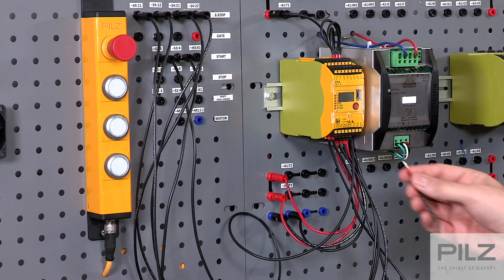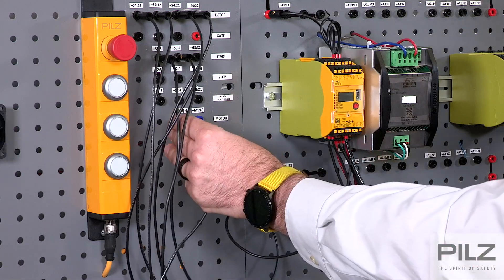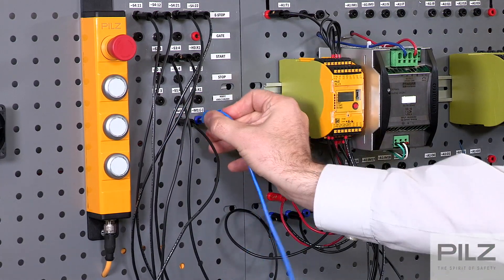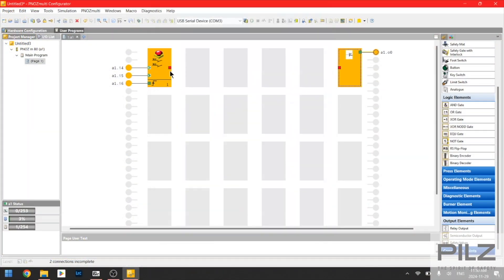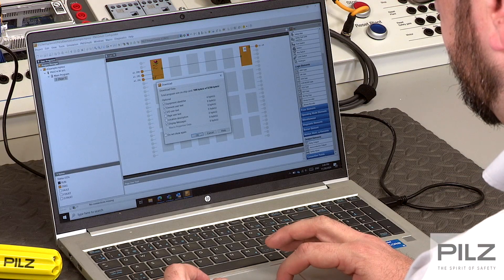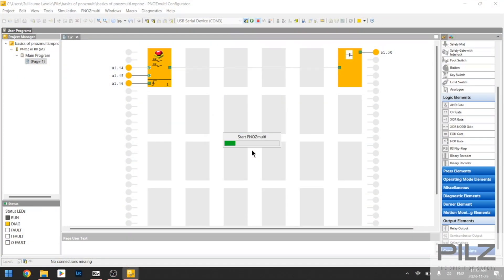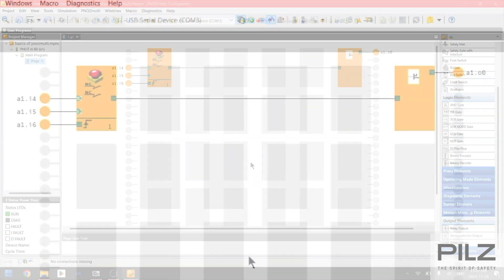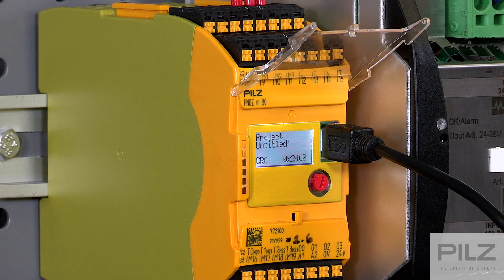Once this is complete, we can now set up an output for your controller. On the PNOZmulti2, there are four transistor outputs rated to 2 amps each. If your application requires it, Pilz also offers expansion cards with relay contacts. A feedback loop to provide higher diagnostic coverage of your system can be configured at this time as well. Once the outputs are wired and the project is downloaded, the controller is ready to safely stop your machine.